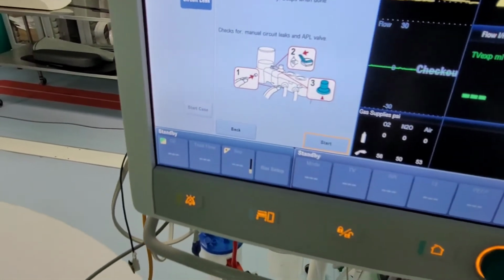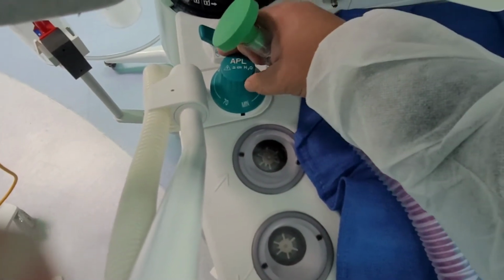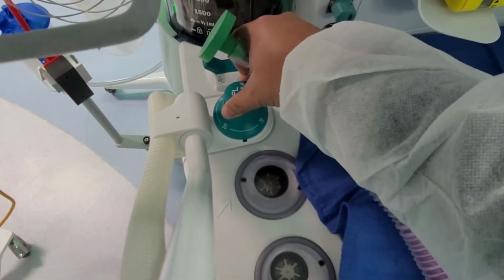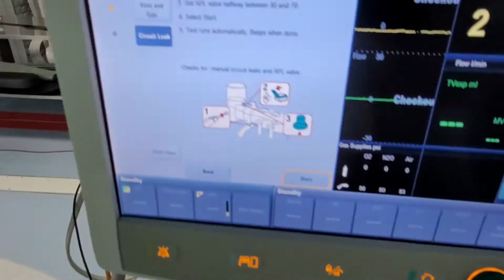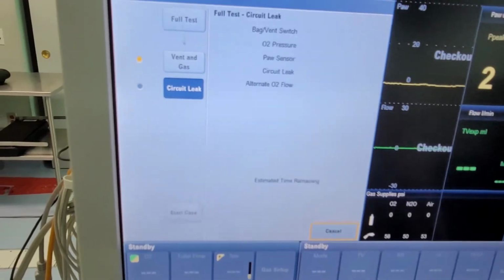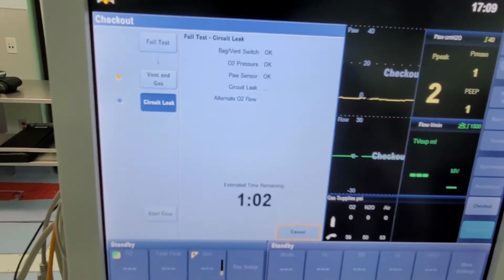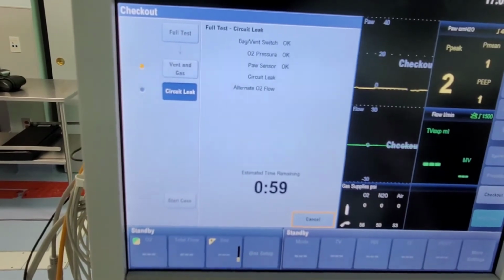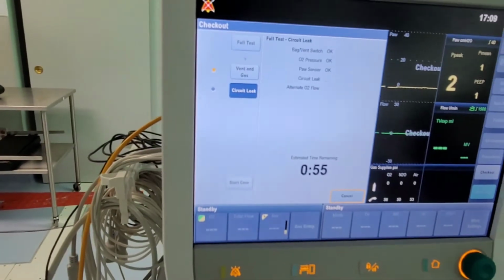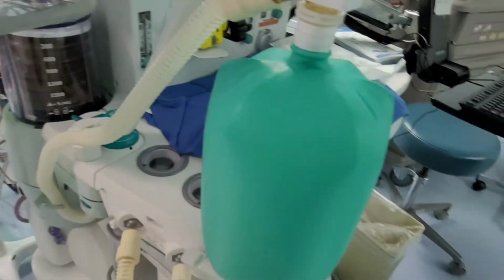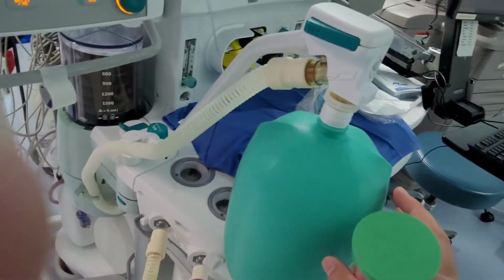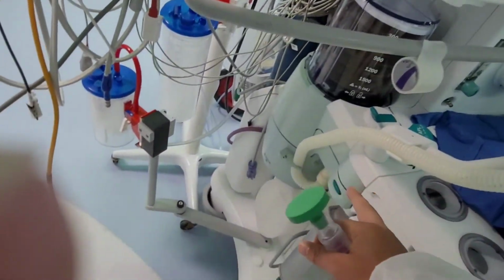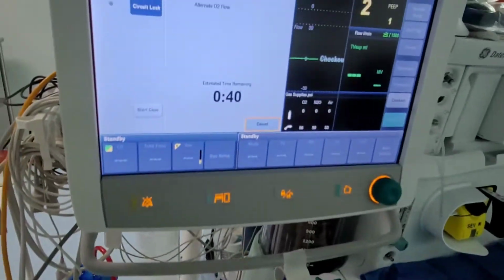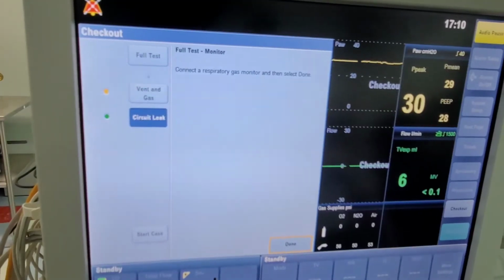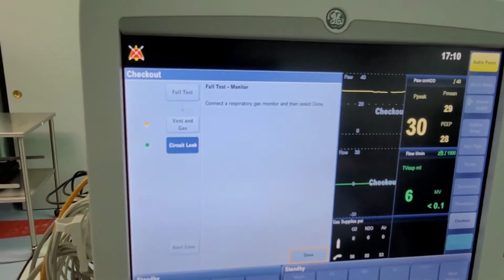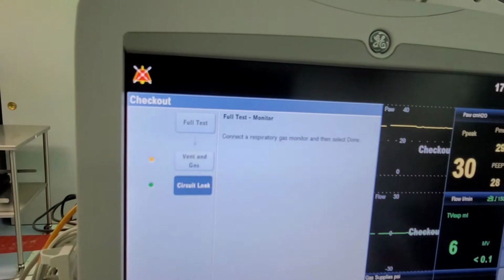Set the APL halfway between 30 and 70. This is your APL valve. Halfway, 30, 70. And select start. These tests are quicker. Same thing, measuring compliance and any kind of leaks between the bag, the reservoir or the manual bag, all the way down into the ventilation system. So it passed the circuit leak.